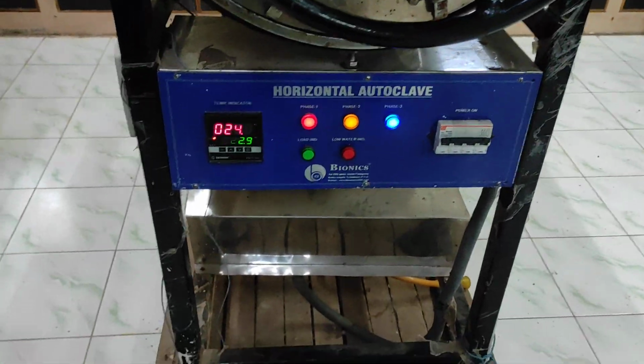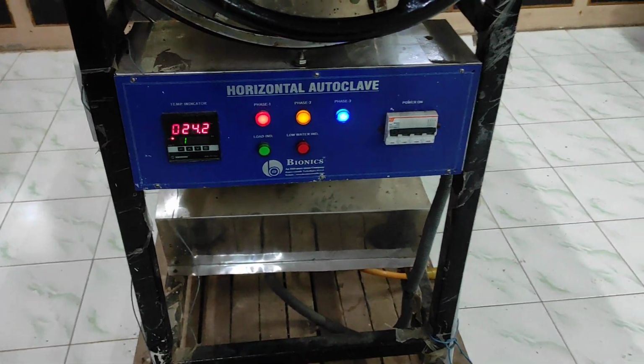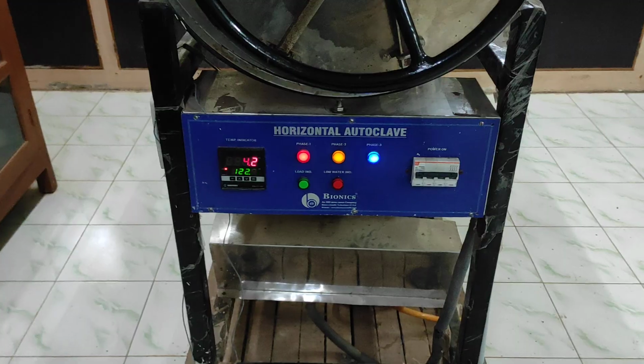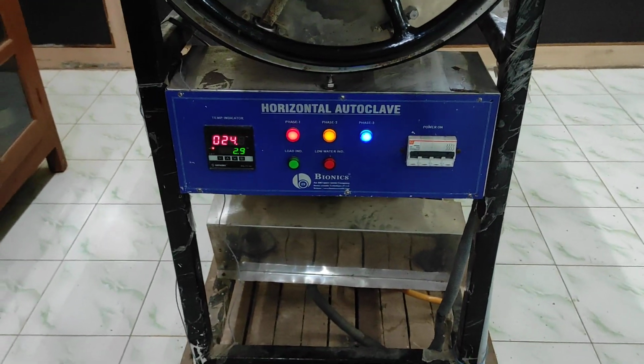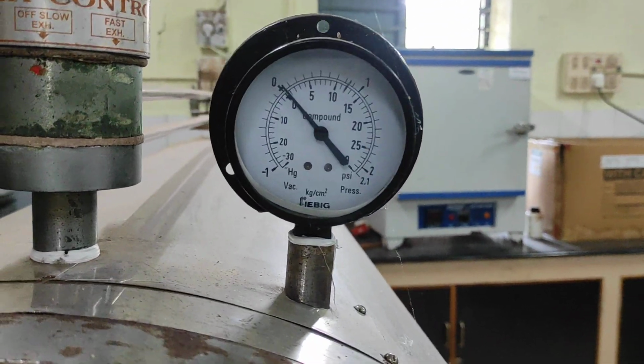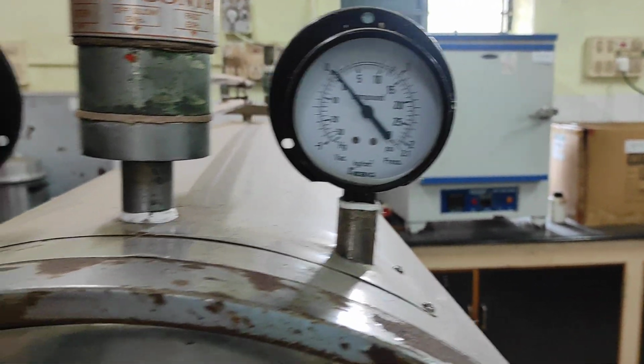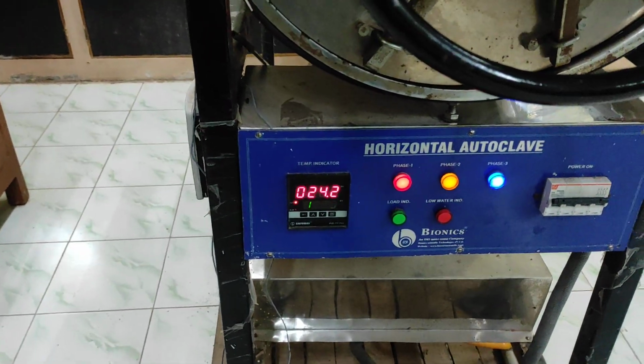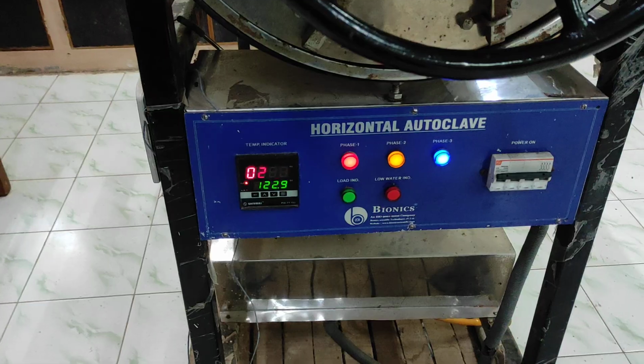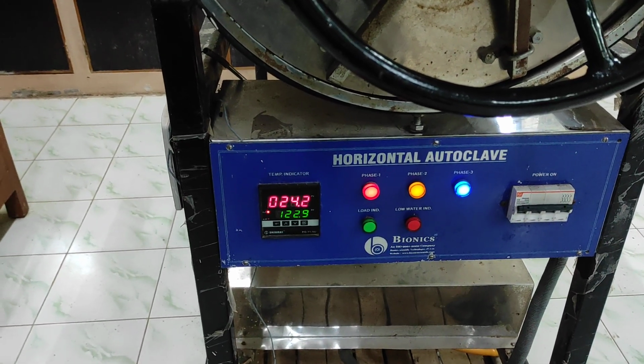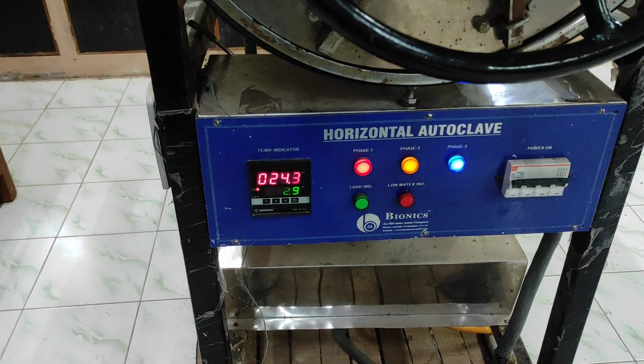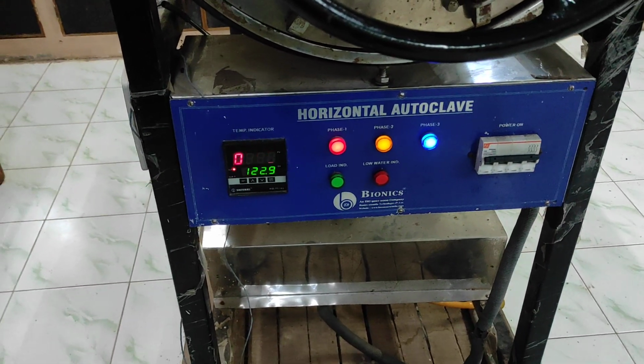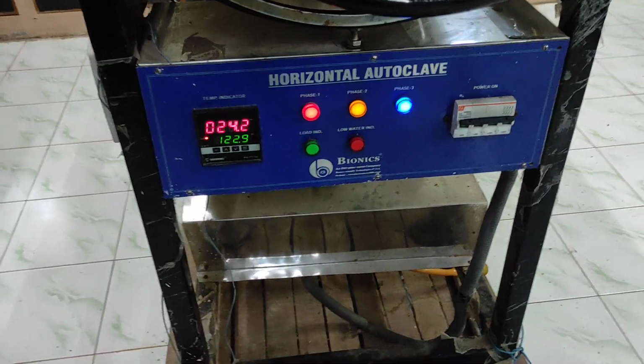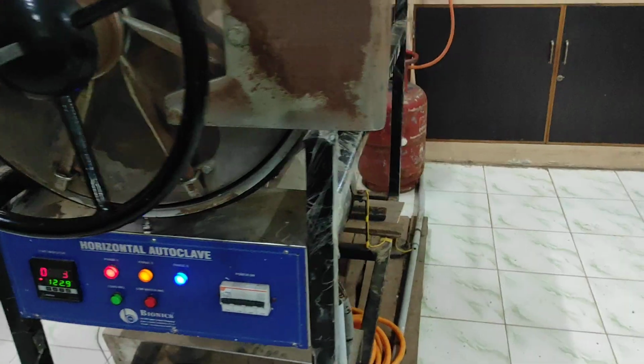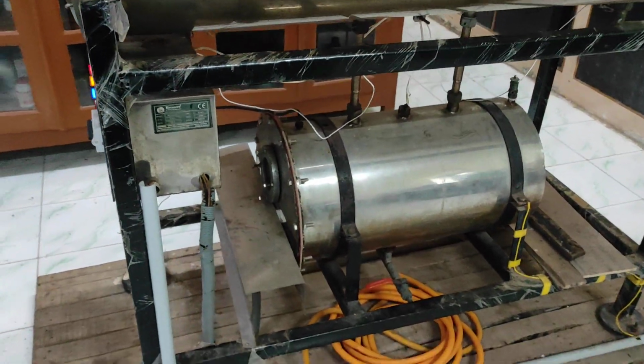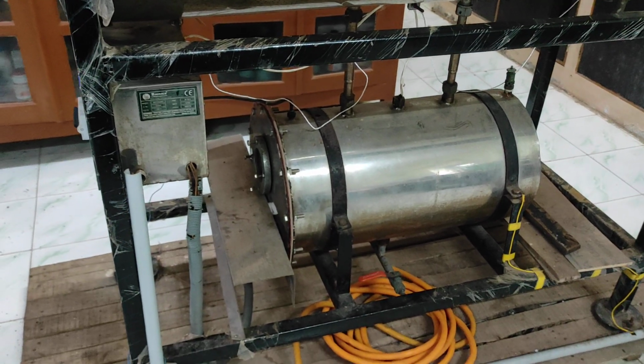So three things are important here. Temperature: generally the temperature we keep, which is considered optimum, is 121 degrees centigrade. The same temperature we keep for 15 pounds of pressure. And then the timing, at least 15 minutes. When the autoclave has been used for many years, we increase the temperature and even the timing, from 15 minutes to 20 minutes, depending on different laboratory setups. Generally recommended is 121 degrees centigrade, 15 pounds pressure, and in general 15 minutes. With these three parameters, everything will be sterilized inside the autoclave.